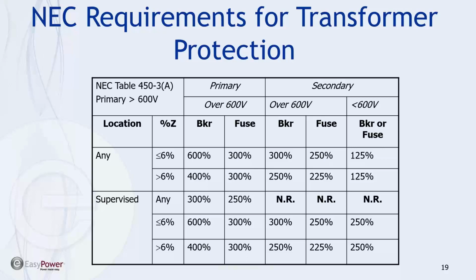Then we need to take into account the recommended requirements for transformer protection based upon the installation conditions in terms of the location, whether or not the equipment's being monitored by qualified people, and the voltage level that the application's installed, and then the impedance ratio of the transformer itself. And so these are the percentage of full load current that the protection needs to take into account for each one of these installations or conditions.